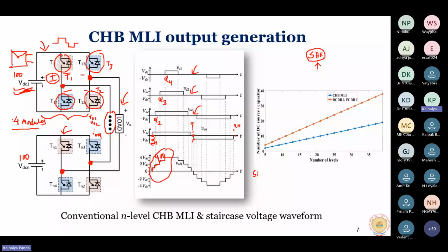Because of that, if I check my total harmonic distortion, the factor generally used to evaluate harmonics, you will realize the THD is reduced from about 40%, which is typical in a 3-level inverter and very high. If you see this type of pattern, and calculate the THD, it will gradually reduce down to about 20 to 25%. I am talking about the voltage THD, not the current THD.